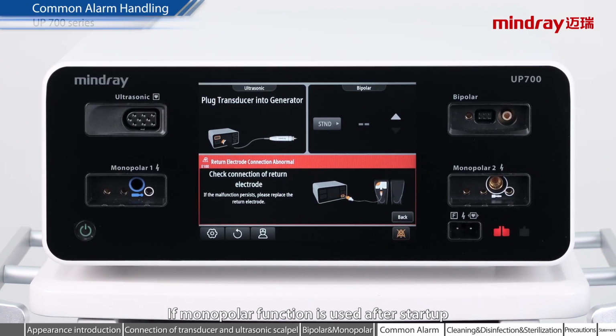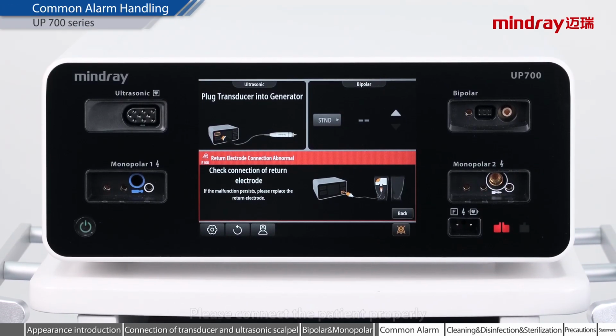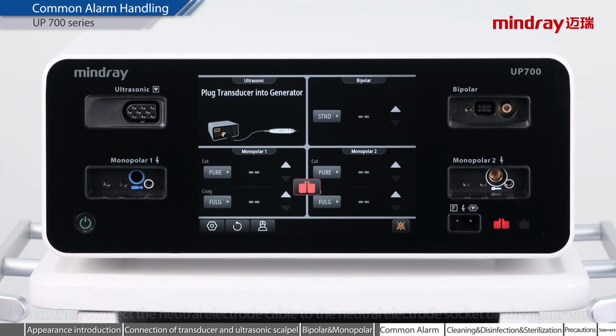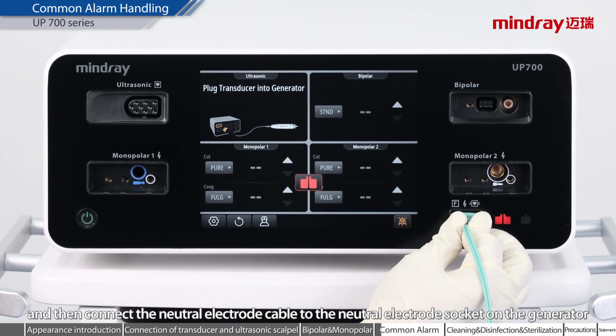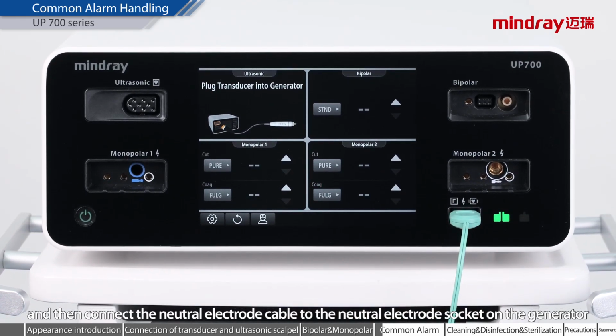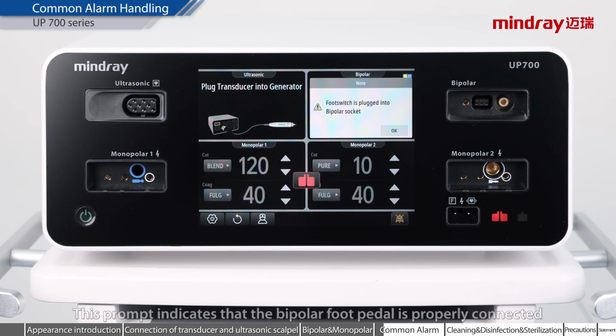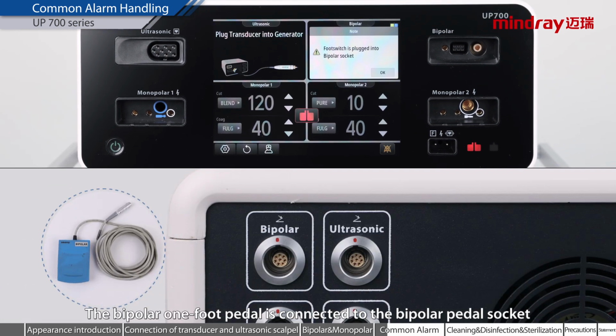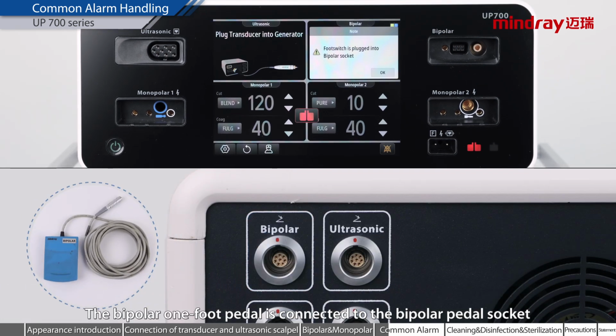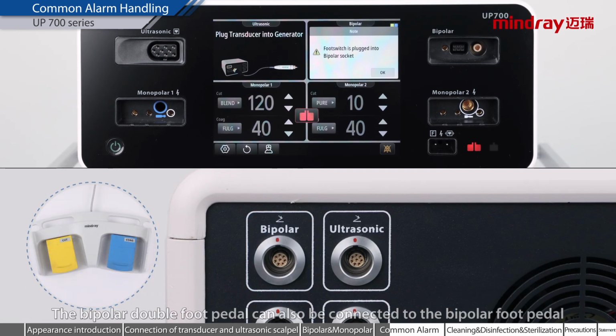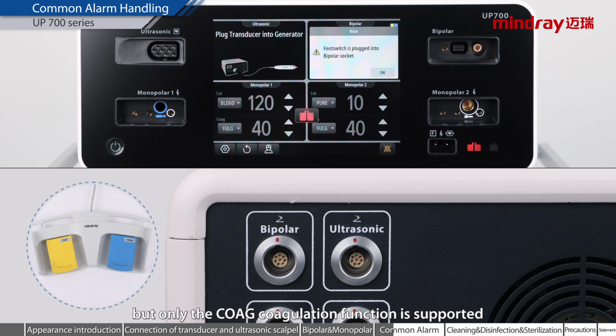If the monopolar function is used after startup, please connect the patient properly and then connect the neutral electrode cable to the neutral electrode socket on the generator. This prompt indicates that the bipolar foot pedal is properly connected. The bipolar 1 foot pedal is connected to the bipolar pedal socket. The bipolar double foot pedal can also be connected to the bipolar foot pedal, but only the coagulation function is supported.